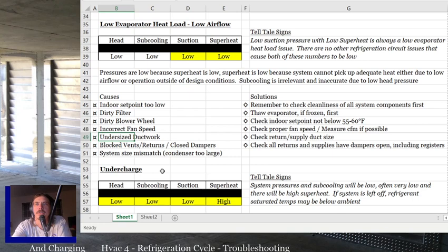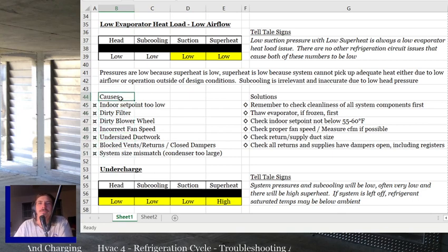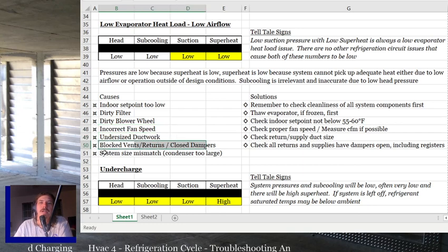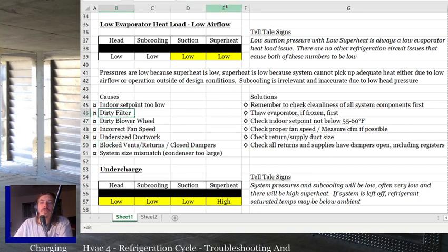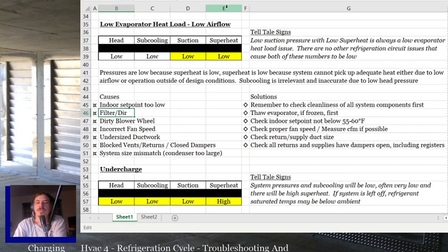Well, I'm trying to tell you. No. I'm trying to tell you right now, right? So these are the possible causes. Indoor set point too low, right? That could be the issue. But 9 times out of 10, it's going to be wrong fan speed, undersized ductwork, blocked vents and returns and closed dampers, or dirty filter or dirty coil. I didn't even write dirty coil on here. I'm going to put dirty coil next to dirty filter. All right.